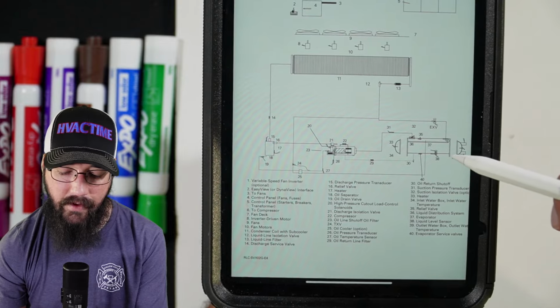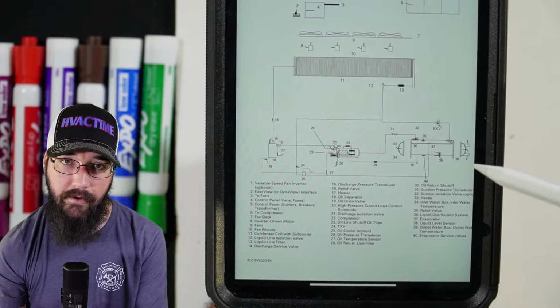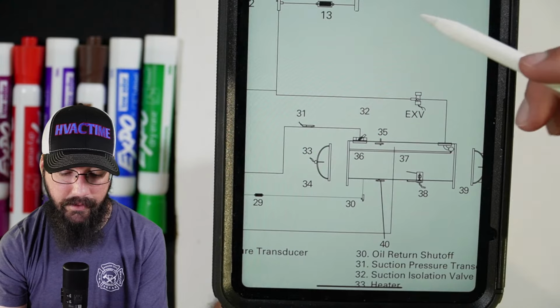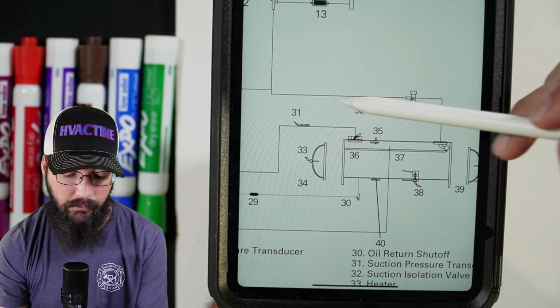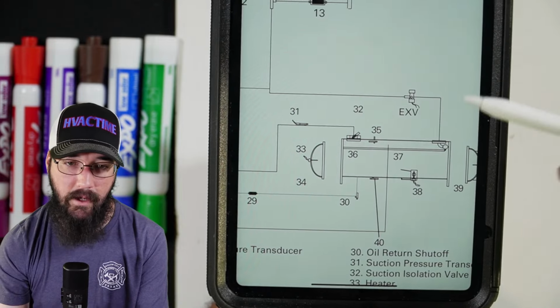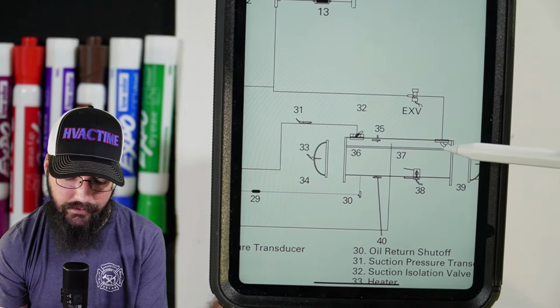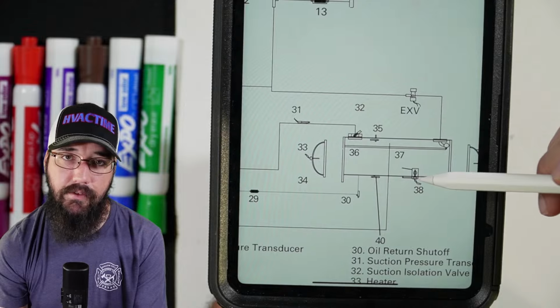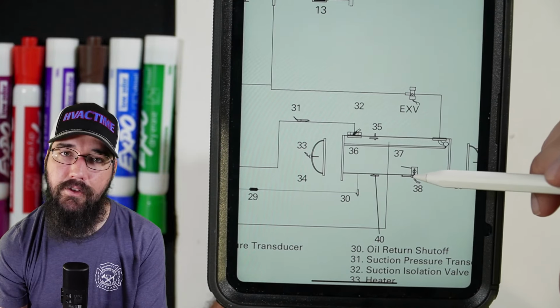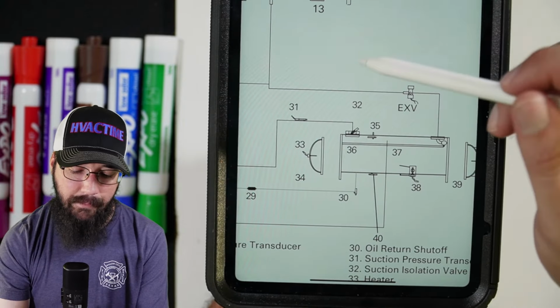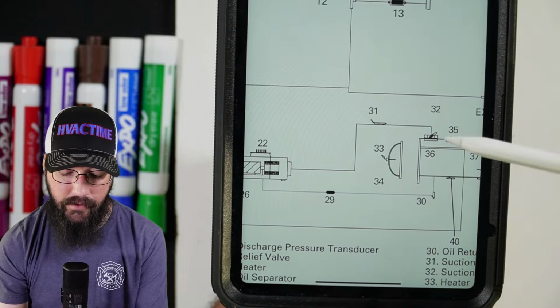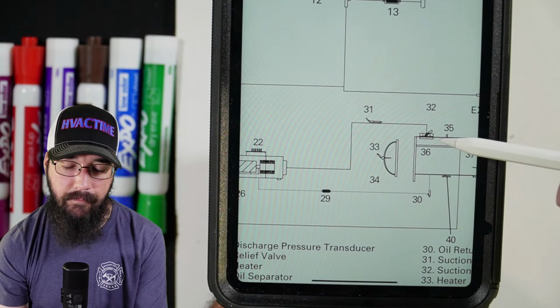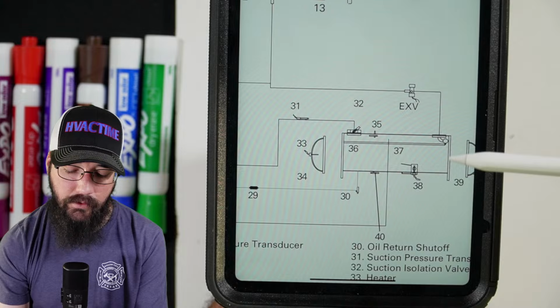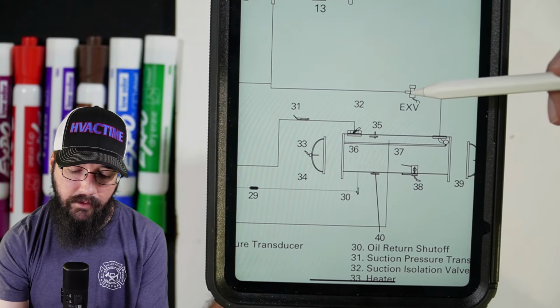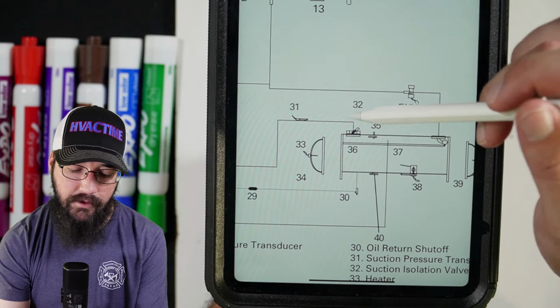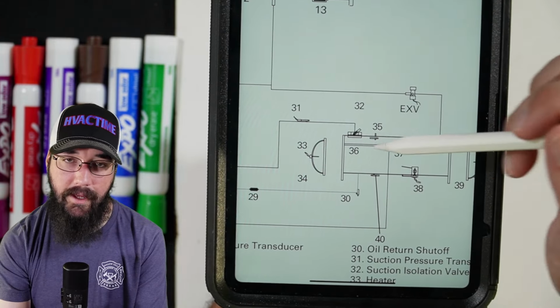Now keep in mind, these evaporators are falling film evaporators. So bear that in mind with an RTAC. If we zoom in a bit here, we come out of the condenser liquid line, and then we come over to our EXV, which feeds into the top spray rail of the evaporator. As we feed in, refrigerant is controlled by a liquid level sensor. It's monitoring and maintaining just a couple of inches of liquid in the bottom of the evaporator. Because this is a falling film, notice that our suction line is on the top of the evaporator. In this evaporator, water is inside the tubes, refrigerant is on the shell side, and our metering device feeds into the top of the evaporator, and our suction feeds off the top of the evaporator. So both connect to the top.